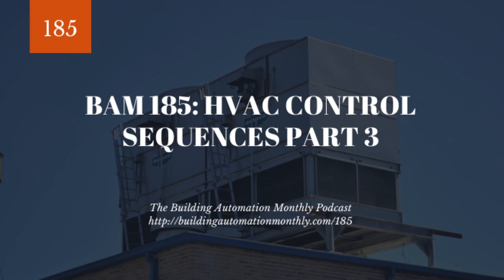On the flip side, if you use a sequencer block, what can happen is that you will not have granularity of control. Once you hit that 50% threshold, that sequencer block is going to come on. Now, there's a variety of different ways. I don't want to get too much into the sequence of programming here, but either one works: PID into a sequencer block, or PI, or just directly controlling into a sequencer block. For some of you who are like, what the heck did Phil just talk about? That makes no sense. I encourage you to go check out our ultimate guide to BAS programming where it talks through sequencer blocks and PID loops and things like that.